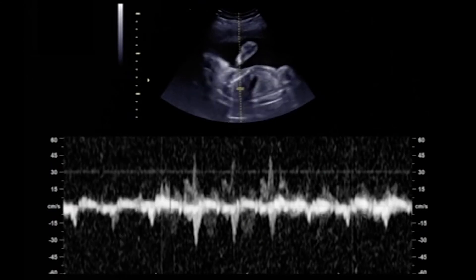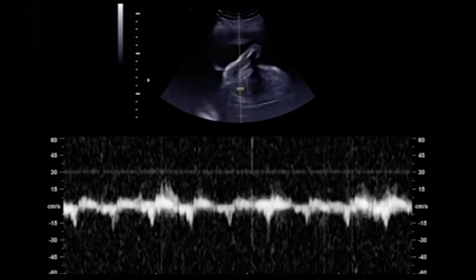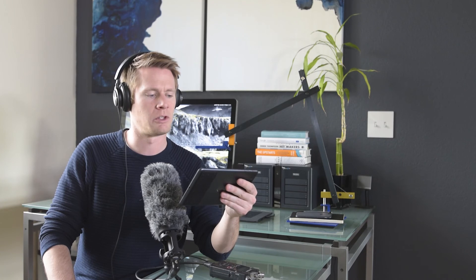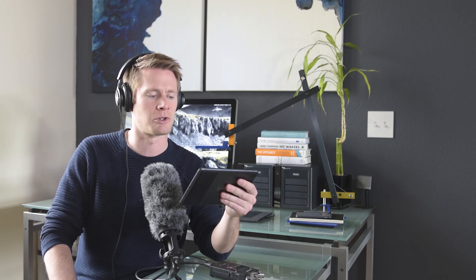The processor can also measure the change in frequency of reflected ultrasound waves to calculate speed — this technique is known as Doppler ultrasound. User interface. This allows the operator to adjust the frequency, amplitude, and pulse duration of the ultrasound waves. Ultrasound waves are typically produced in the range of 1 to 18 megahertz. Lower frequency waves travel deeper into the body but produce lower resolution images. Higher frequency waves do not travel as deep but can produce higher resolution images of smaller structures.